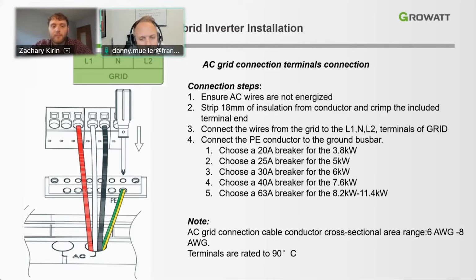This will probably also be a quick reminder for people that there are basically 3 different units that Growatt makes. So there is the 3.8 and 5 kilowatt, which have 2 MPPTs, then the 6 kilowatt to 7.6 kilowatt that have 3 MPPTs, and then the larger ones from there, 8.2 to 11.4, will have 4 MPPTs. So also, depending on your roof, you have to make sure you select the right inverter. So it's not just strictly about oversizing anymore. The price difference between all of these is not huge, but just keep it in mind that, for example, the 5 kilowatt only has 2 MPPTs. And if you have 3 roof sections that you want to utilize on a roof, select the 6 kilowatt or 7.6 kilowatt inverter in that scenario.